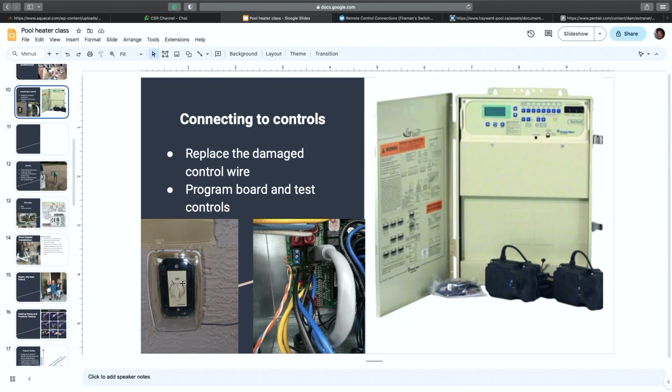And what that means is that the contact doesn't have its own source of electricity. When it closes, the wires you hook up to it are what allow electricity to pass through it. So basically your pool heater generates the signal to go through that circuit, and if it closes, it gets that signal back. And it knows, okay, this path is closed, I can activate pool mode or spa mode, whatever it is. That's a dry contact. So when you look through an install manual and they say make sure it's a dry contact, just think of an open-close switch.